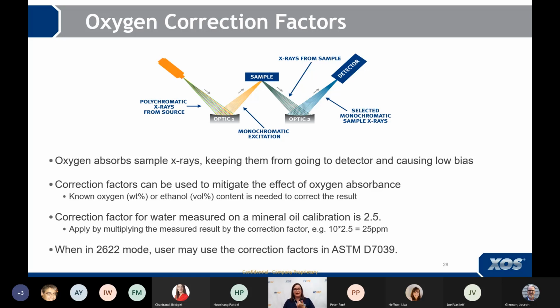So when you're measuring a biodiesel or an E10 on a mineral oil calibration, or, we commonly get asked about water. A lot of people end up running water on their Cloras, and the correction factor for that is 2.5. That means it measures 2.5 times lower when measured on a mineral oil calibration. So in order to correct for that, you take your measured value, in this case 10 is my example, and multiply it by the correction factor to get your oxygen corrected value.